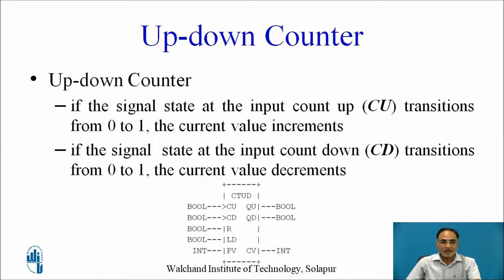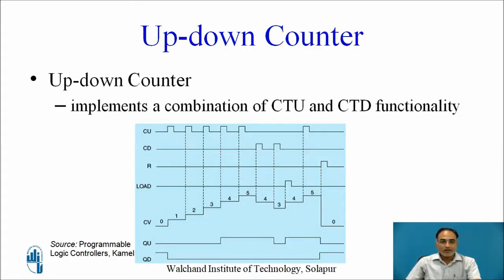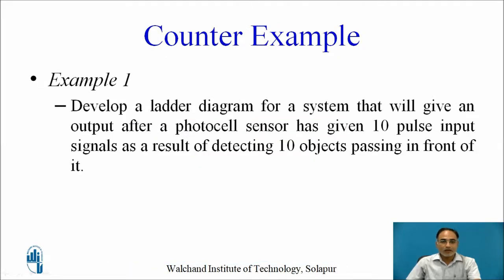The up-down counter allows both up and down counting. If the CU signal transitions from 0 to 1, the current value increments; if the CD signal transitions from 0 to 1, the current value decrements. The waveform shows that with pulses applied to CU the CV increments, and with two pulses applied to CD the counter value decrements by two.